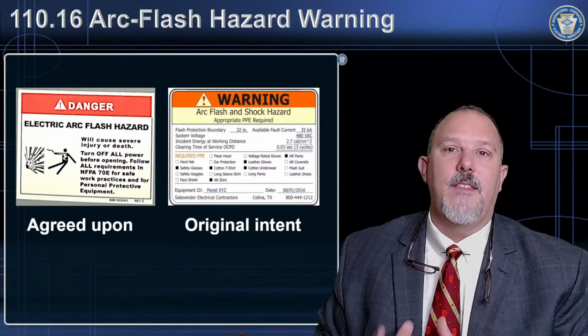Get your copy. Arc flash. It is the light, the heat, the sound, the gases. Everything that goes into an unintended rapid disassembly in the field is happening right here, okay? This is something that our electrical industry unfortunately lives with. I can have my opinion that we don't have to live with this, because there are ways to avoid this, to reduce the occurrence of these events. We don't have to necessarily live with these events because we can design around them. But this change was driven out of events like that.